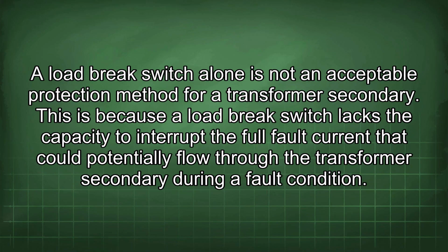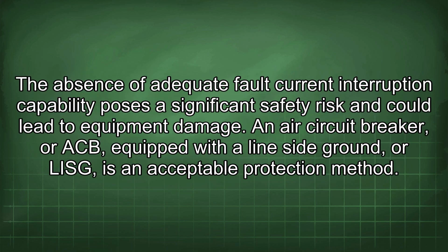A load break switch alone is not an acceptable protection method for a transformer secondary. This is because a load break switch lacks the capacity to interrupt the full fault current that could potentially flow through the transformer secondary during a fault condition. The absence of adequate fault current interruption capability poses a significant safety risk and could lead to equipment damage.